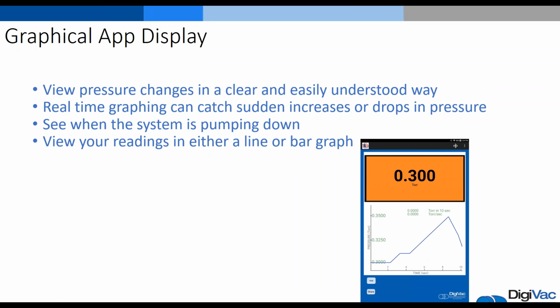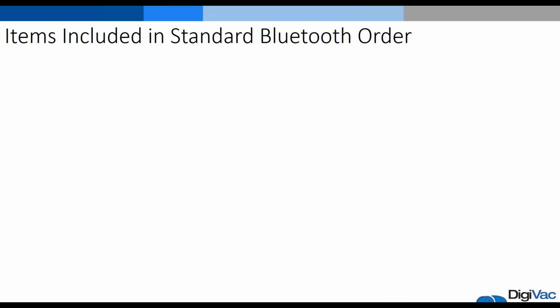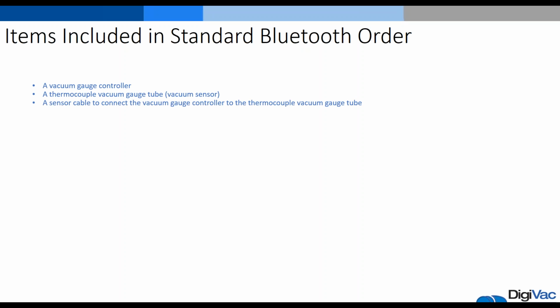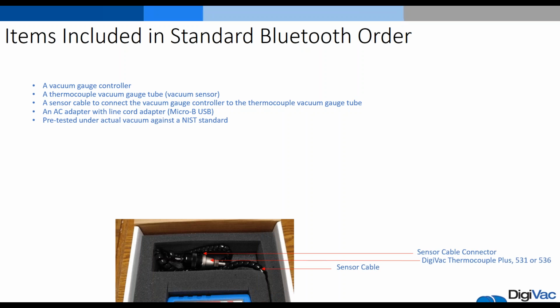And that's an image of the Bullseye gauge pressure being read on the vacuum gauge app and displayed within a line graph. So the items included in a standard Bluetooth order for the Bullseye are the vacuum gauge controller, the thermocouple sensor, and a sensor cable that can connect the gauge controller to the sensor. And then an AC adapter that allows you to plug the gauge into a USB port. And then everything's tested under actual vacuum against the NIST standard.